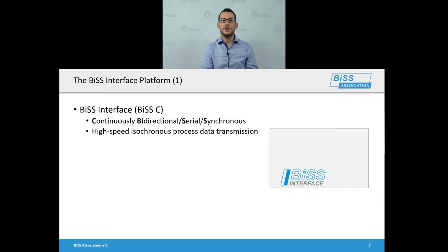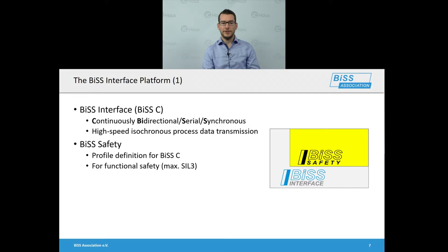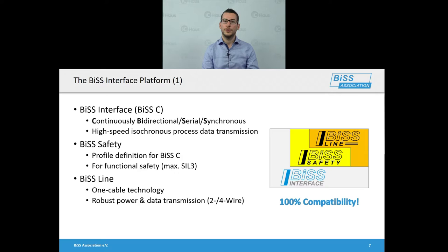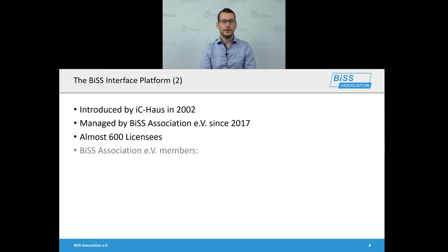A short overview about the BiSS interface platform. When we talk about the BiSS interface we talk about the BiSS-C protocol. BiSS stands for a serial synchronous interface that enables continuous bi-directional data transmission. It is typically used in motion control and motor feedback applications because it enables high-speed isochronous process data transmission. BiSS Safety is a profile definition that enables using the BiSS interface in safety-critical applications up to SIL3. BiSS-LINE is the one-cable technology, enabling robust power and data transmission over only two or four wires. Importantly, all these aspects are fully compatible with each other.